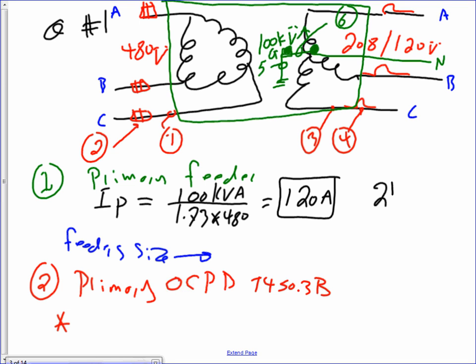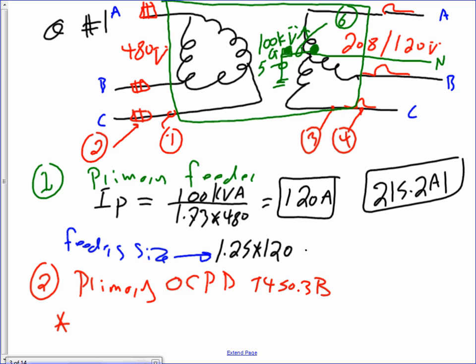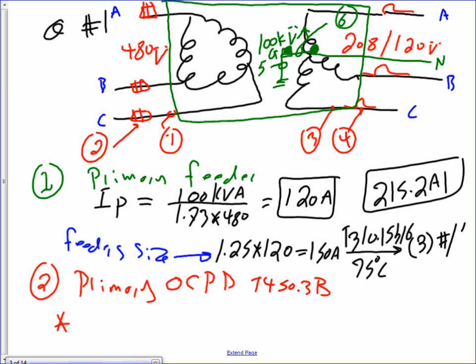Now, if you go to 215.2(A)(1), the feeder section in the NEC code book, it will tell you if it's a continuous load. If it's a continuous load, size it by 1.25. We're sizing a feeder, so it's a continuous load, 1.25. Multiply this by 120. It will get you a healthy 150 amps. Take this, gentlemen and ladies, to the 310 table, 310.15(B)(16), under the 75-degree column.